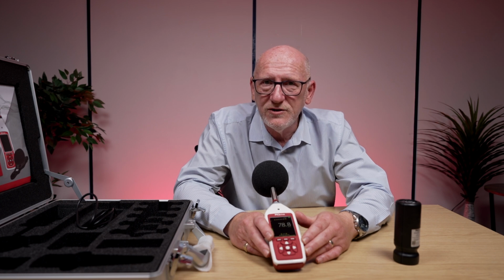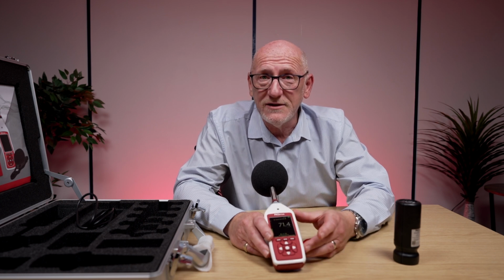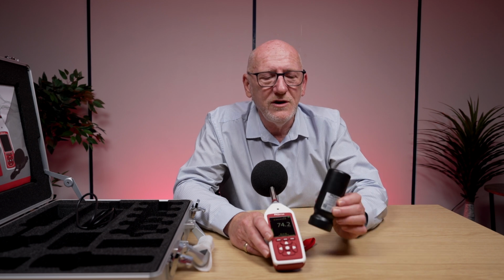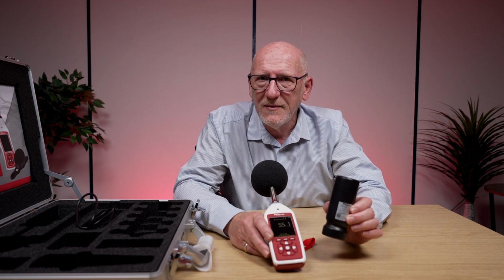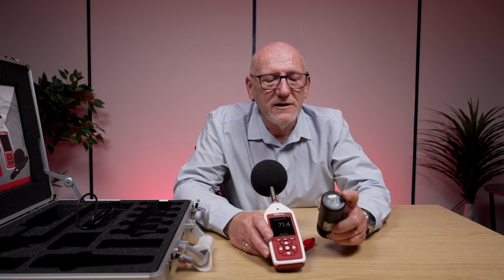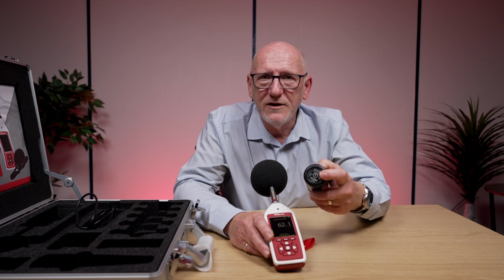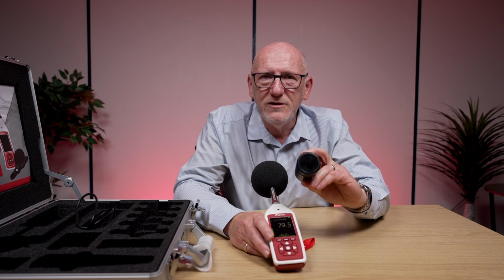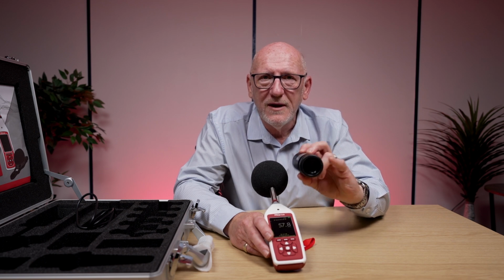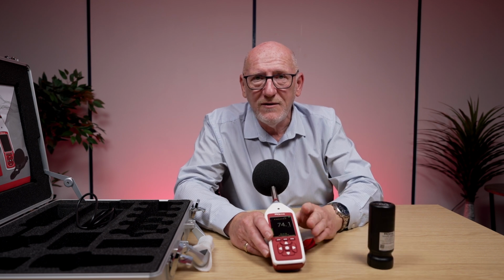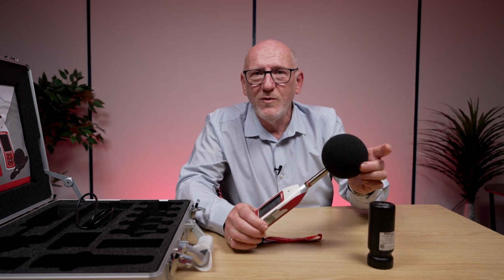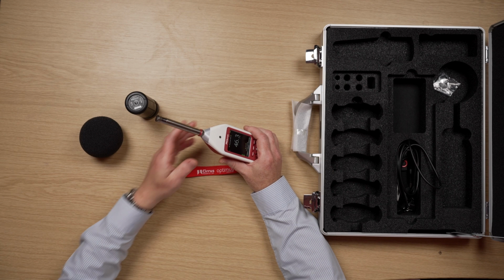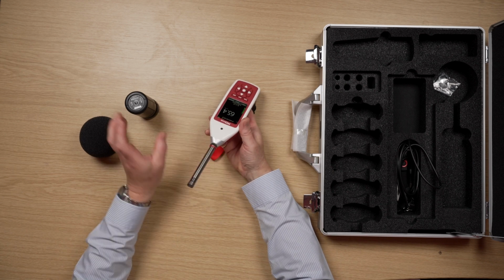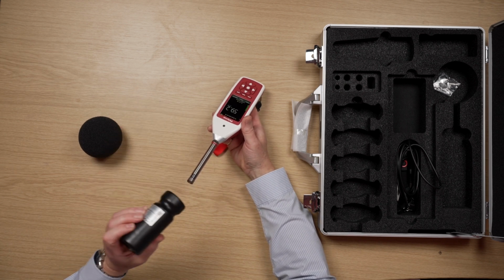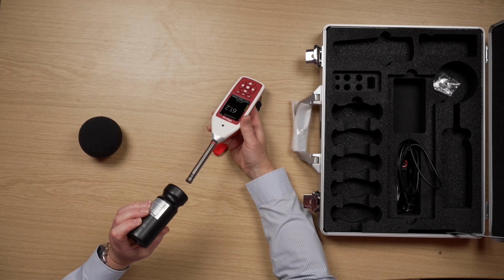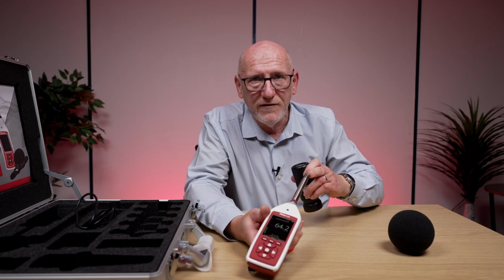So let's do a calibration. We're going to use obviously our sound level meter, and we're also going to use our calibrator. So the calibrator has a button on the top to turn it on and off, and then on the base you'll see a small hole. And what we're going to do is we're going to take our sound level meter, we're going to remove the windshield for this exercise, and then what we're going to do is we're going to place the calibrator on top of the sound level meter directly onto the microphone.